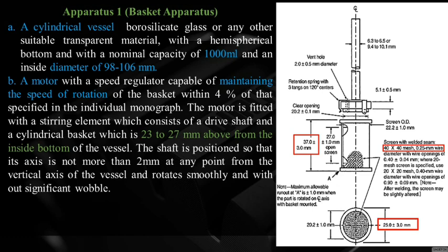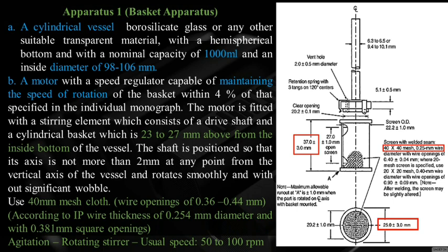The shaft axis must not deviate more than 2 mm from the vertical axis of the vessel at any point. Rotation should be smooth with no significant wobble. The basket consists of a 40-mesh cloth with wire openings of 0.36 to 0.44 mm. According to IP, wire diameter is 0.254 mm and openings are 0.381 mm square. According to USP, wire diameter is 0.25 mm, basket length is 37 ± 3 mm, and outer diameter is 25 ± 3 mm.